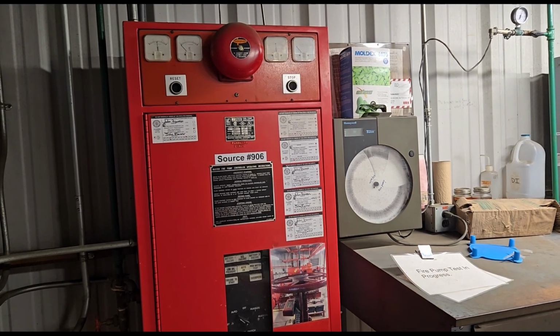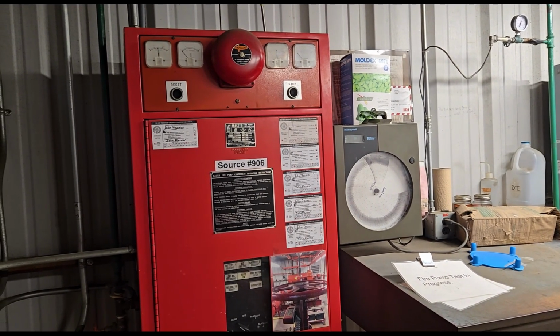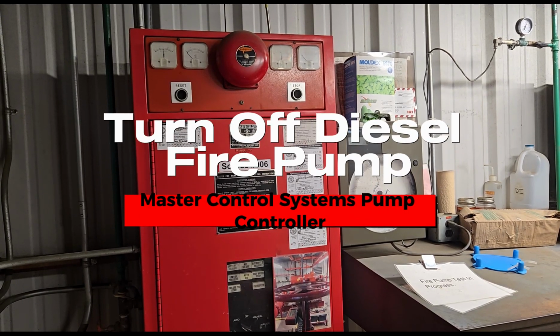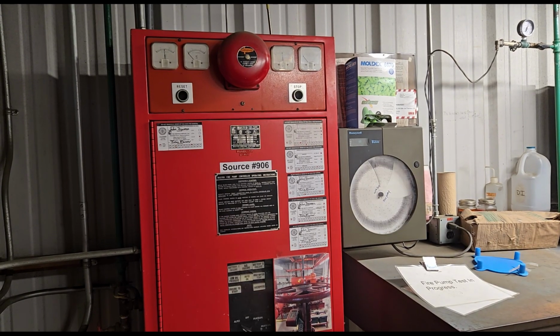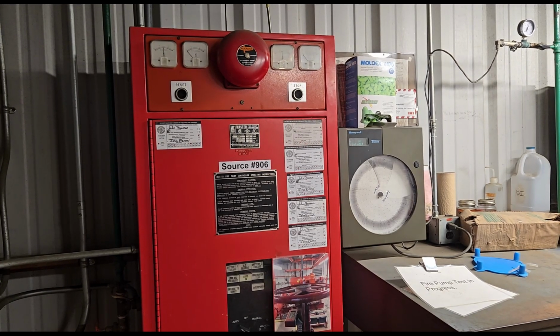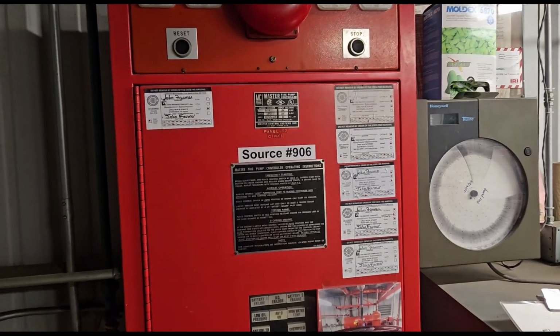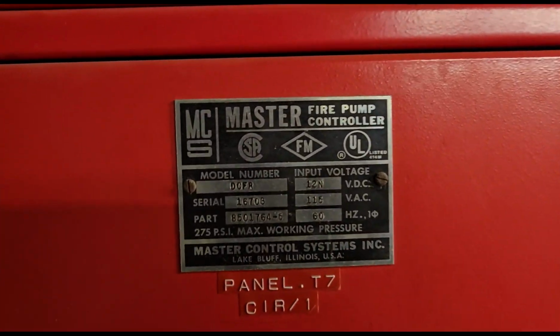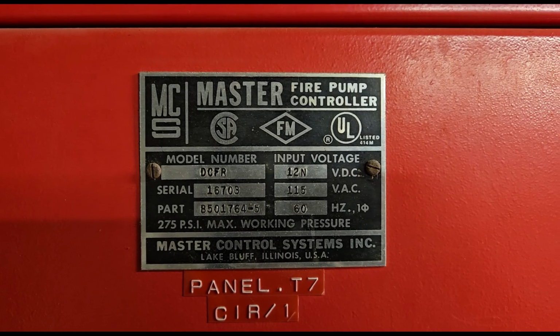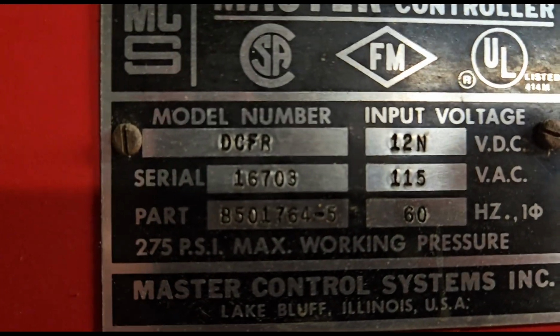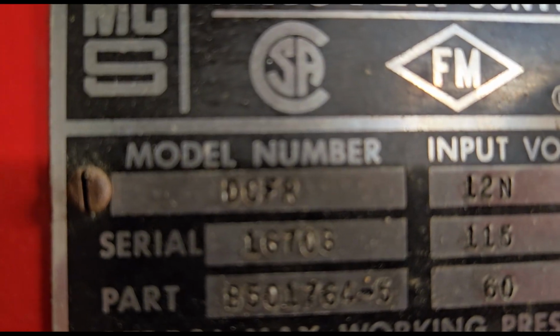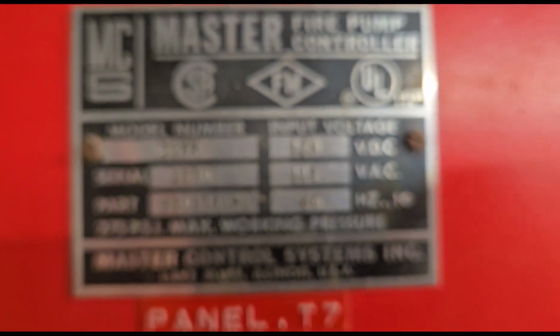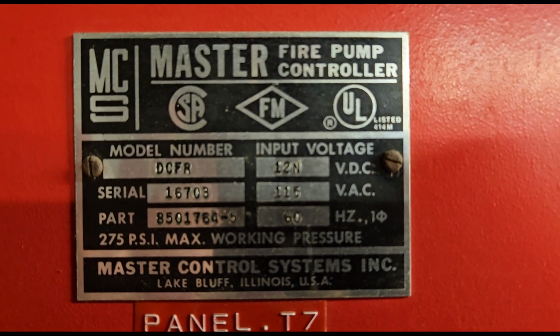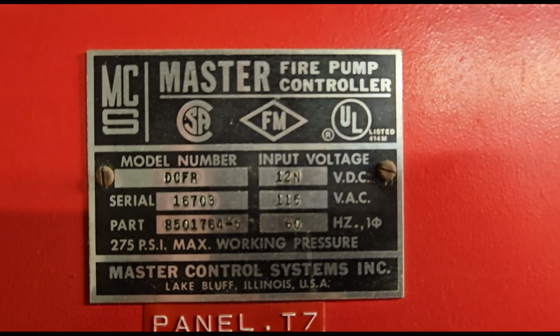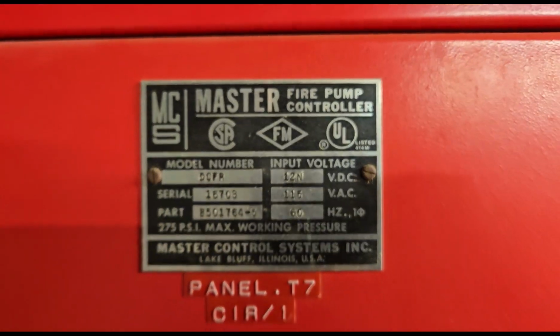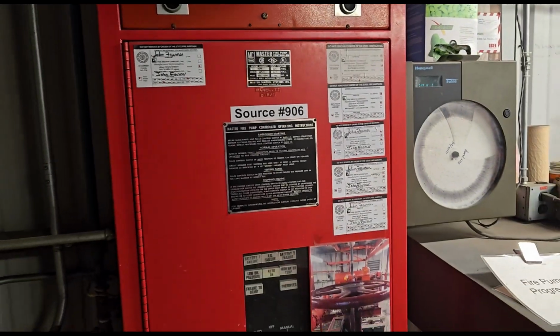In this video, I'm going to show you how to bypass or turn off the diesel fire pump controller so you could do your flow testing without turning on the fire pump. This is a Master Control Systems fire pump controller, and the model looks like DC-FR. It's kind of hard to see. There you go. Hopefully that gives you a good reading of the calculation plate. So it's Master Control Systems. It's a diesel fire pump.